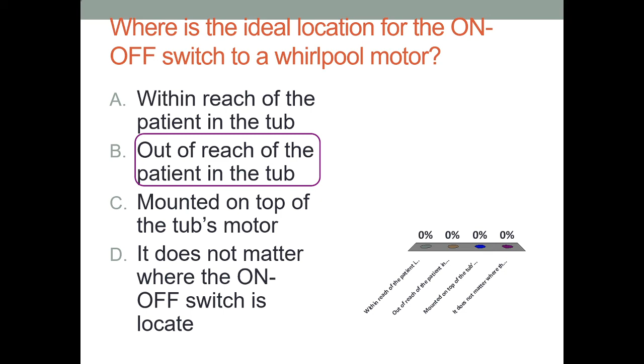Right, and as you guys have all checked off on, you're not supposed to turn the motor on or off when they're in the whirlpool, because during those times is the biggest time for a possible short circuit. The GFI should catch it, but again, even then, a momentary shock would be problematic. So ideally, that switch would be in an area that the individual could not reach, thereby eliminating the potential problem. Now, I've never seen that actually done in that way, so it's one of those reality versus optimal situations.